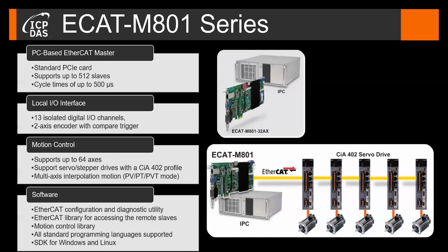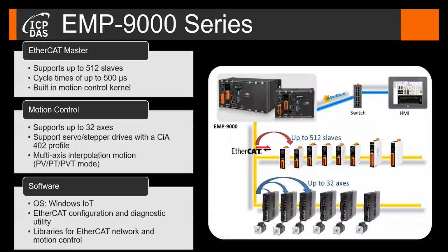The slaves with CiA 402 profiles are automatically detected and configured by the EtherCAT master to simplify the integration. The motion engine generates several types of motion profiles, including point-to-point, linear and circular interpolation, and contouring. The product comes with an extensive software package, such as a software utility and workbench for configuring, testing and diagnosing the EtherCAT network. All libraries for motion control execution and for direct data exchange with remote slaves are available. The libraries can be linked to any standard programming language.